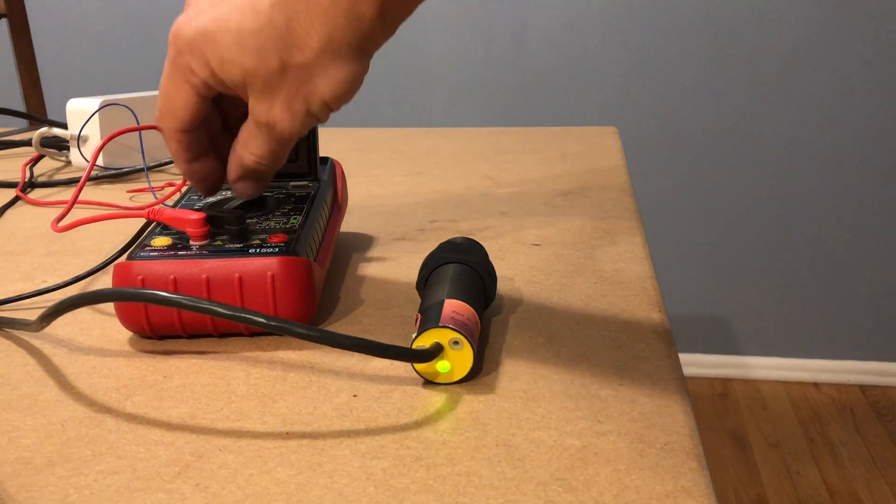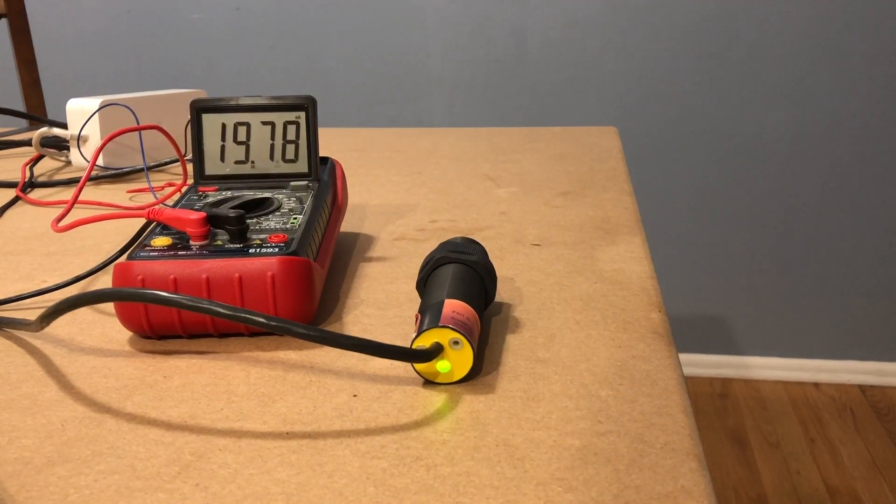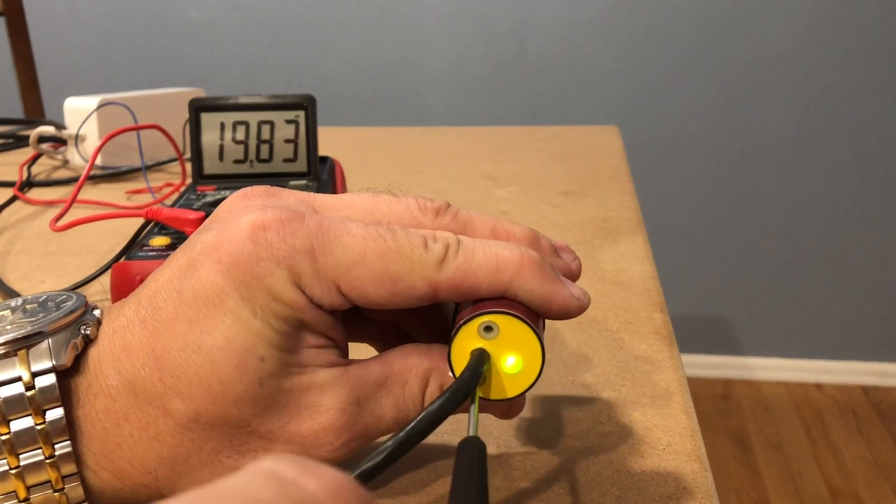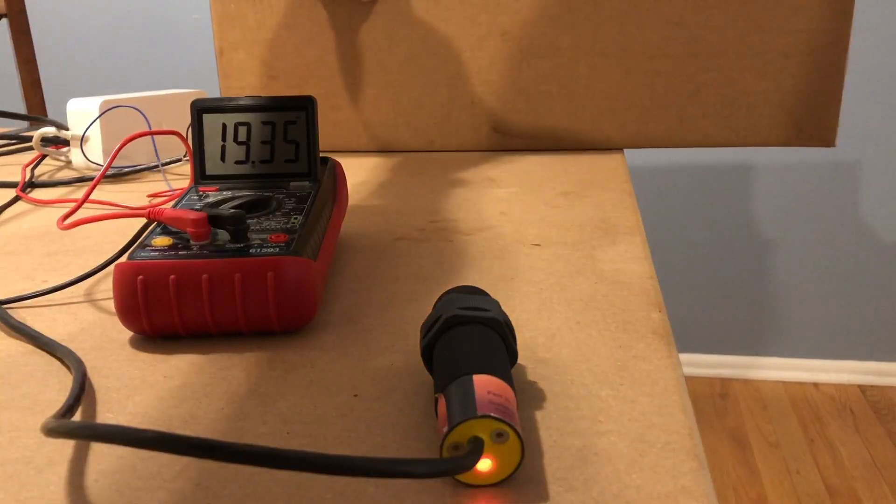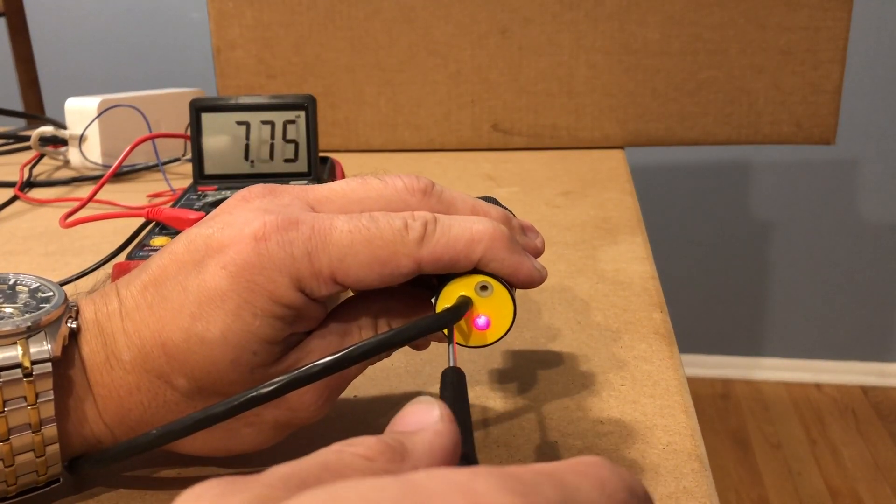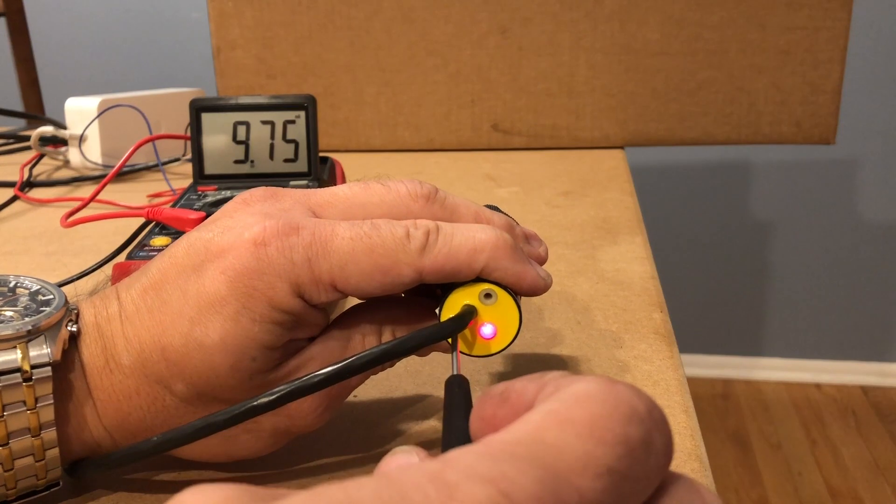The sensor has two potentiometers built-in. These are called span adjustment. After playing with them for a little bit I found that one controls the far end distance and the other one is for the close end.